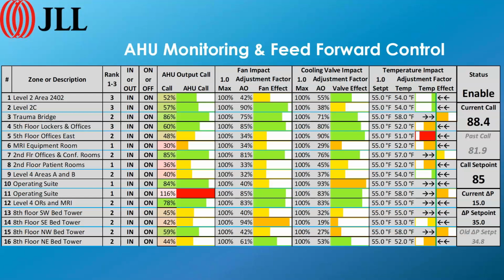And so that is a load on the air handler that the fan power boxes are saying, hey, we've got some load. Let's figure out what's happening, and let's try to bump that fan up and try to get more out of the fan, try to get more out of the air handler. There is some fan speed. That is a response to what's happening with the VAV portion, the airflow portion of the system.